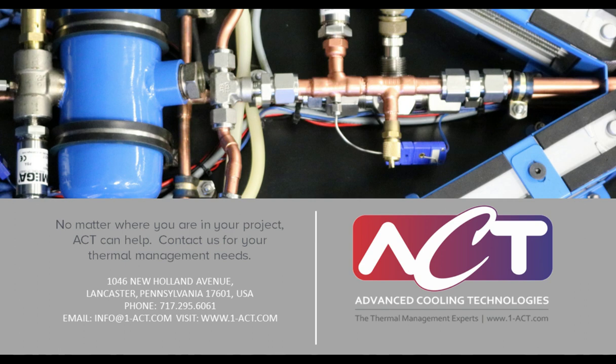Thank you. Next question. Are pumped two-phase cooling systems typically pressurized? And if yes, what are the typical values? They are. They often use refrigerants like R134A or R245FA, and those refrigerants are not liquid at ambient pressures. So the system does need to be pressurized. Typical pressurization ranges from 50 to about 250 psi, depending on the operating temperature of the particular component. There's an entire library of working fluids that we use here at ACT, and we weigh the benefits of using a higher pressure fluid versus a lower pressure fluid and what kind of system level thermal performance we can achieve.